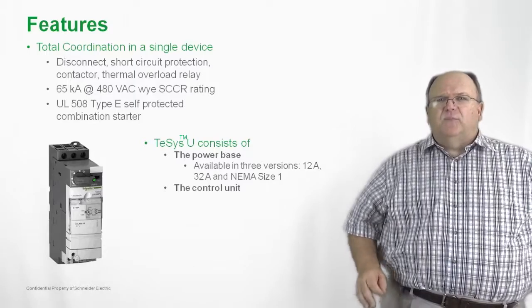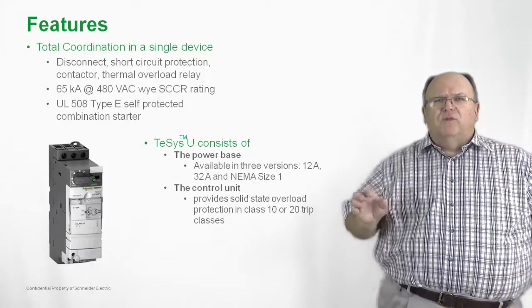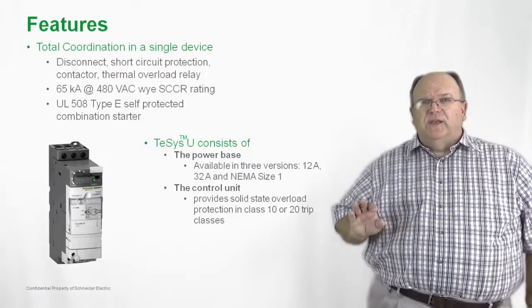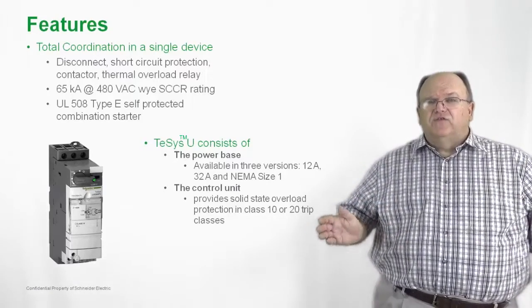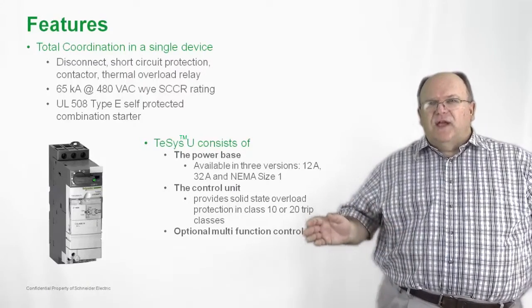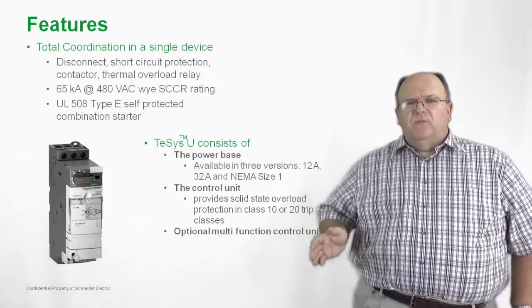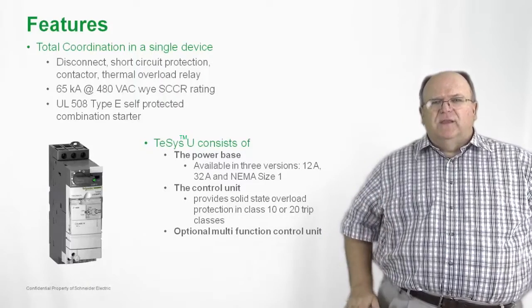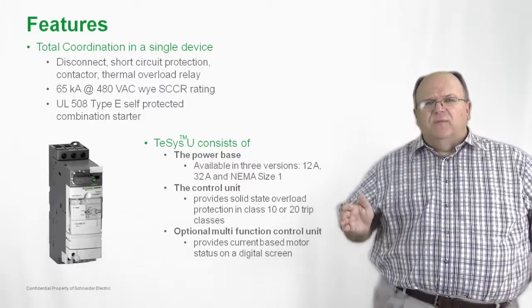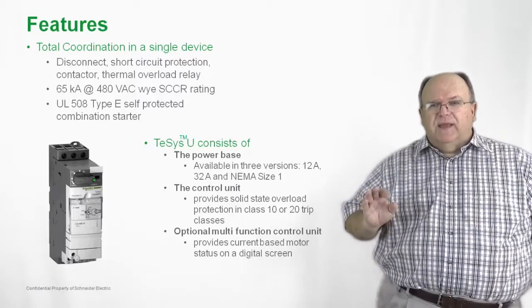The other component that's part of the TeSys U is the control unit. The control unit provides overload protection, and it's available in three different configurations, as well as in either a class 10 or a class 20 trip class rating. We have a number of different options from the standard control unit to the advanced control unit, and also a multi-function control unit which includes an LCD screen to give you current-based information, including a digital readout for the actual current draw of the motor at any given time.